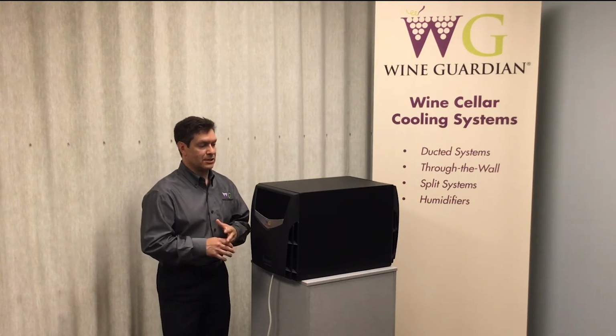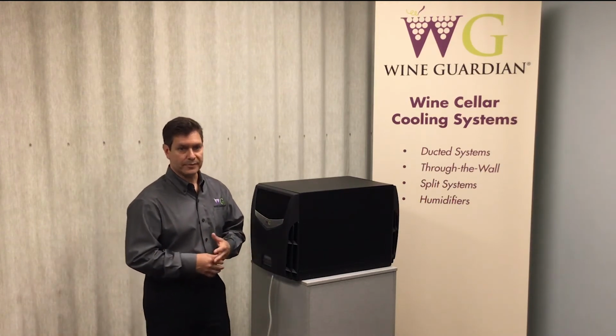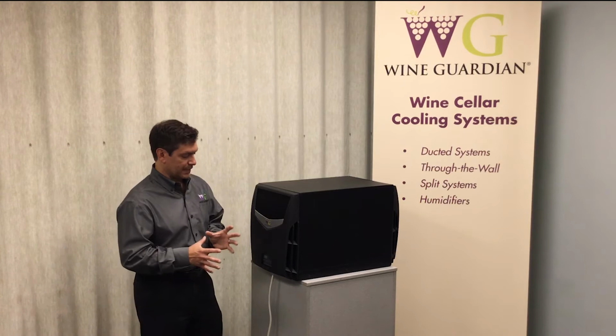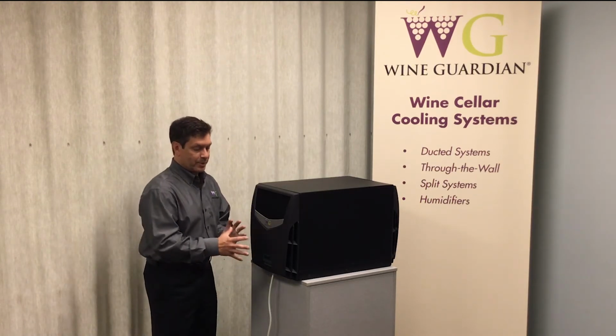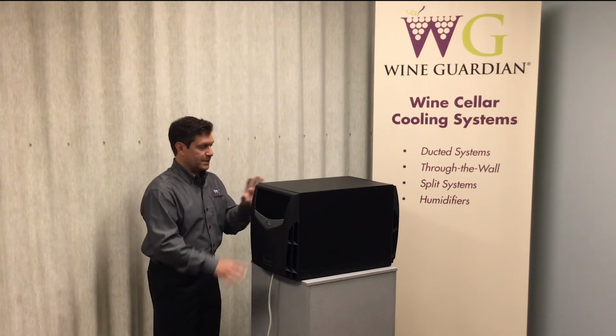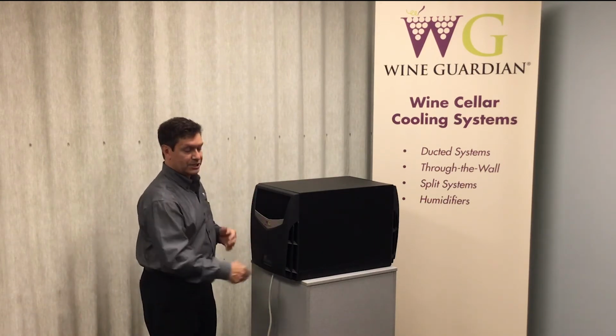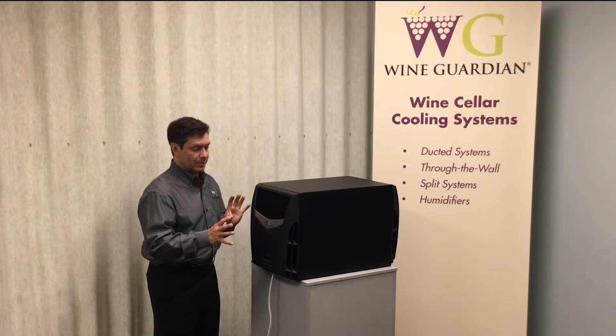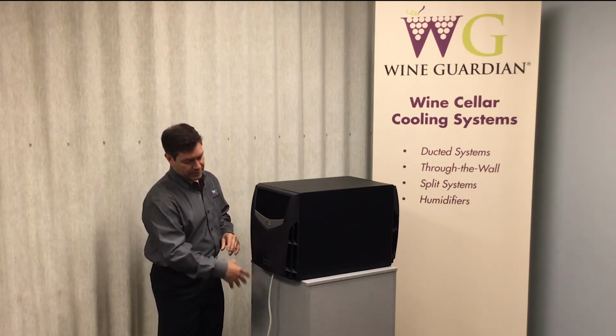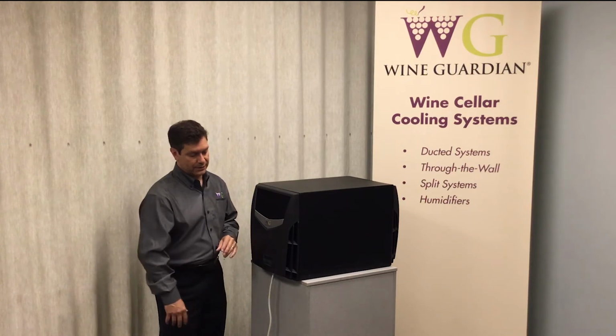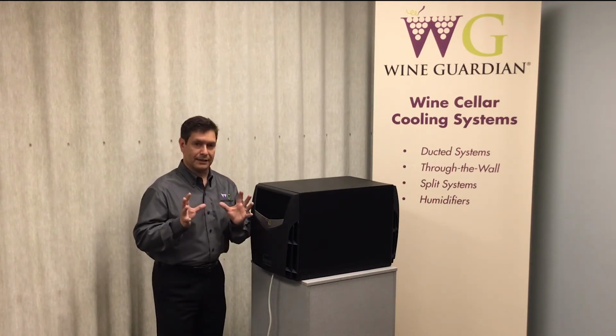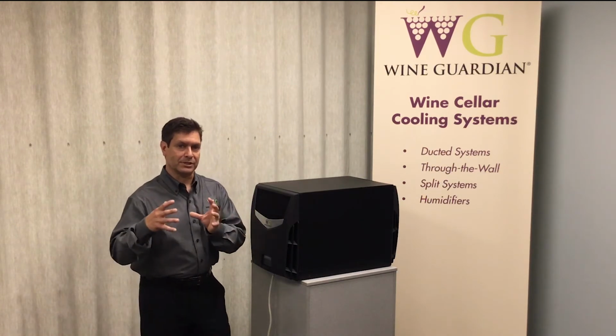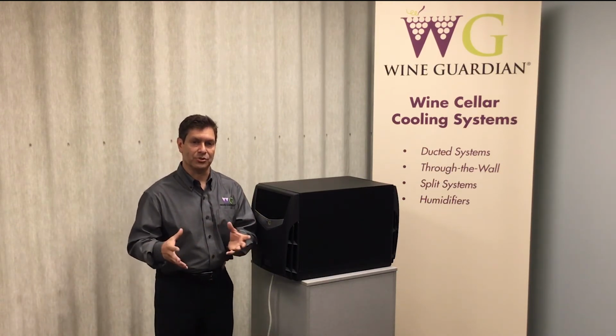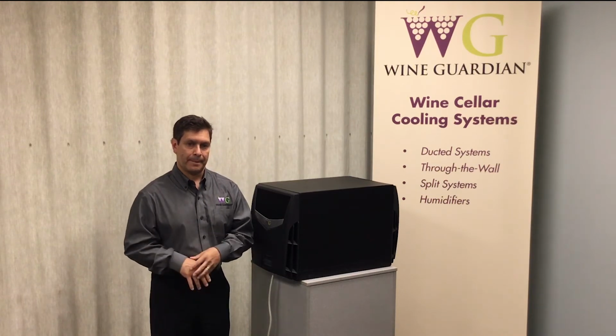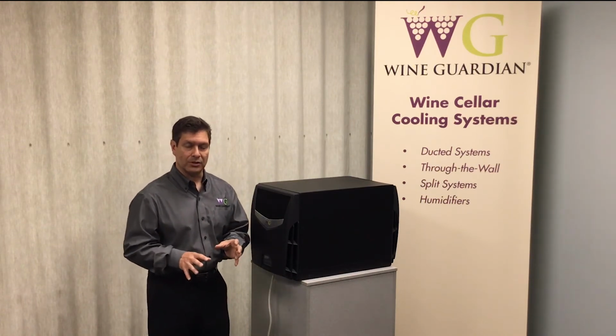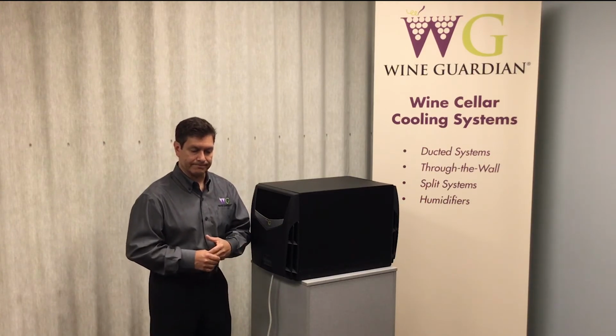One of the other options is the use of our standalone humidifier. The standalone humidifier actually gets all of its control and all of its power through this device. When we take the front and back covers off, we'll show you where the connection to the humidifier is located. Essentially, it plugs into the through-the-wall unit. All the control for the humidity is right here at the front of the system, as we mentioned. That is a separate piece, a separate device that mounts inside the wine cellar, and that adds moisture to the wine cellar space. So that's another option. It's our standalone Wine Guardian humidifier.